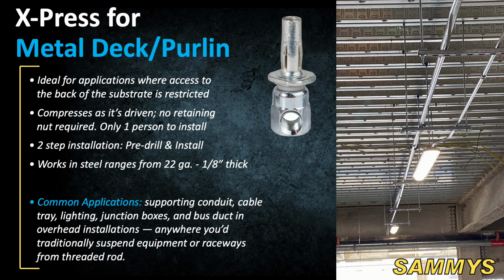When you move into roof deck, pan deck, or purlin applications where you don't have access to the backside, the X-Press system comes into play. The Sammys X-Press anchor is ideal when you're working in metal deck where a traditional through bolt and nut simply aren't possible or are very difficult. As you drive the anchor, it compresses and forms a cross-shaped configuration behind the deck, locking it in place. This gives you a secure point to hang threaded rod for conduit, tray, or lighting from metal roof or floor deck systems.